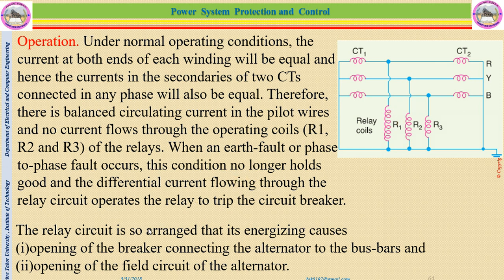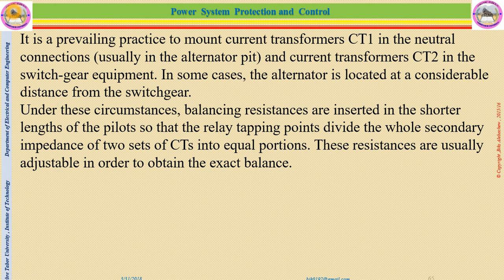So the relay circuit is so arranged that its energizing causes opening of the circuit breaker connecting the alternator to the busbar and opening of the field circuit of the alternator. So the relays will operate those two critical points. It is a prevailing practice to mount current transformer CT1 in the neutral connection, usually in the alternator pit, and current transformer CT2 in the switchgear equipment.